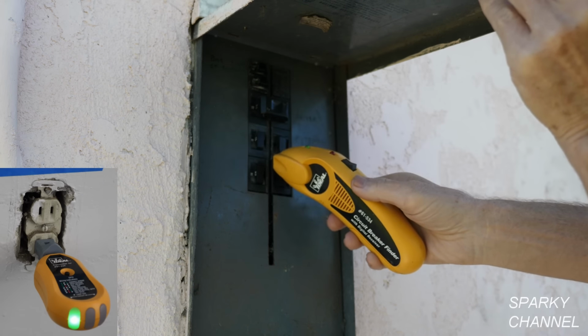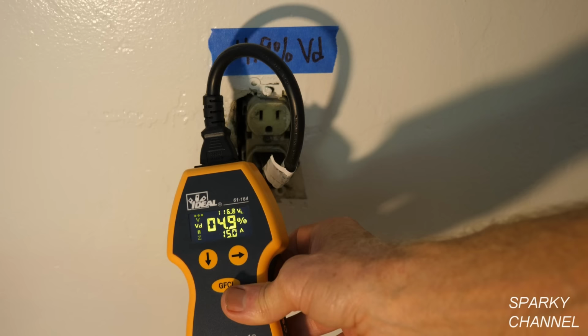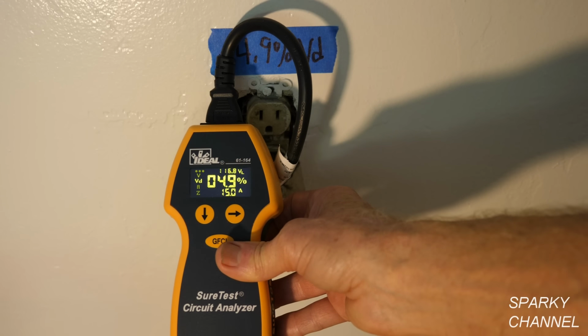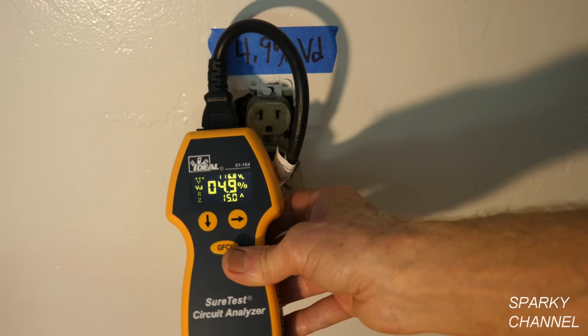So what I'm going to do on my blue tape here, I'm going to write down 4.9%, big V, little d, voltage drop. 4.9% voltage drop. And the receptacle that has the least voltage drop should be the most upstream receptacle, being the receptacle where you would want to put the ground fault circuit interrupter. So I'm going to go around, I'm going to get all the voltage drops of all 7 receptacles, and it's going to tell me a story. Testers like this, if you use them enough, they talk to you, they tell you things, you know. So I'm going to just go around and see what's happening with each receptacle. This adjacent receptacle with a 15 amp load is 6.7% voltage drop.